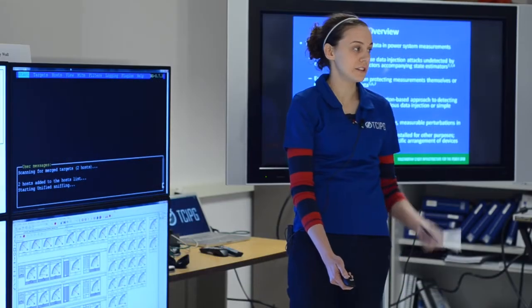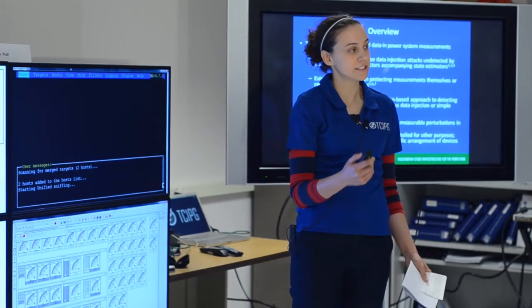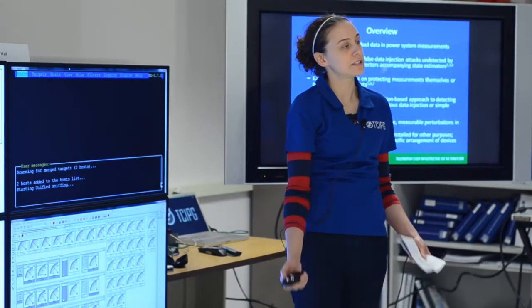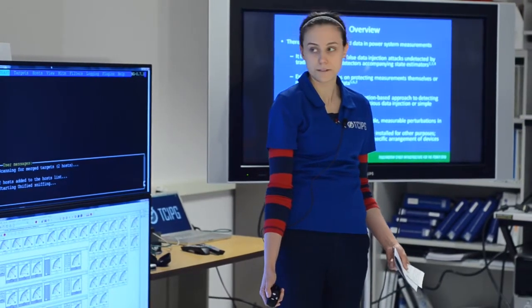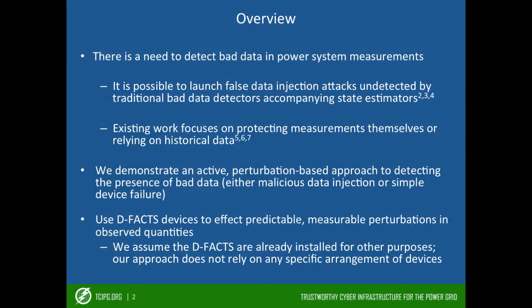The motivation for this demo is that there's a need to detect bad data in power system measurements. It's been shown that it's possible to launch false data injection attacks that could remain undetected by the bad data detectors accompanying traditional state estimators. Existing work on mitigating these attacks focuses on either protecting the measurements themselves or leveraging historical data, but here we're demonstrating an active perturbation-based approach to detecting the presence of bad data, which could be either malicious data injection or simple device failure.